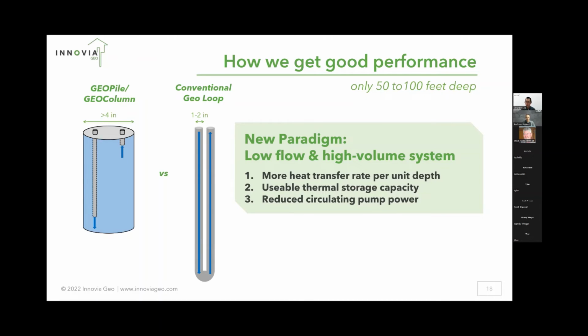And so with that design change, what we do is we have a much larger surface area in contact with the ground per unit depth. So we're able to get more heat and exchange more heat with the ground per depth than a conventional geothermal loop. The other piece there that's very important is this usable thermal storage capacity, and that arises because of the fluid volume in the system. So if you think of a 4-inch pipe compared to a 1 to 2-inch pipe, there's a lot more fluid in the system. And what we're finding with our testing is that we can utilize that fluid as a heat battery and a thermal battery. And I'll get more into details later on about that.